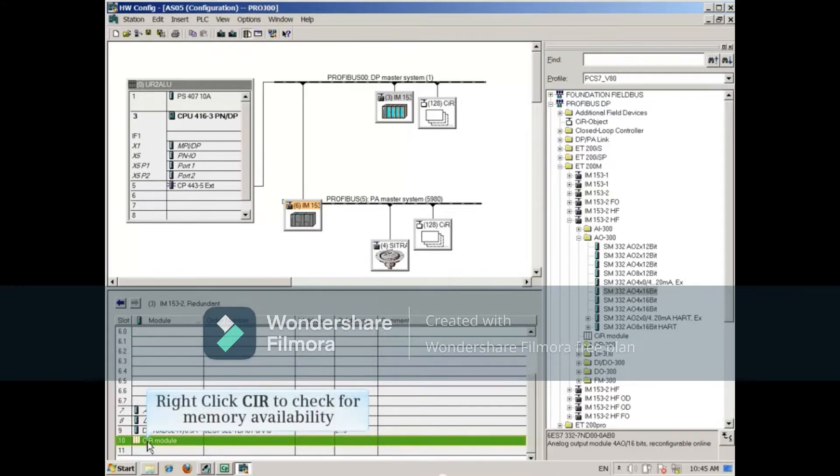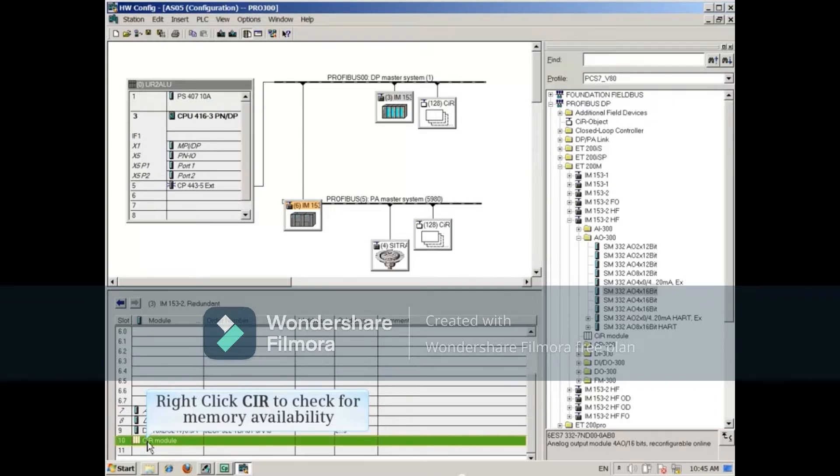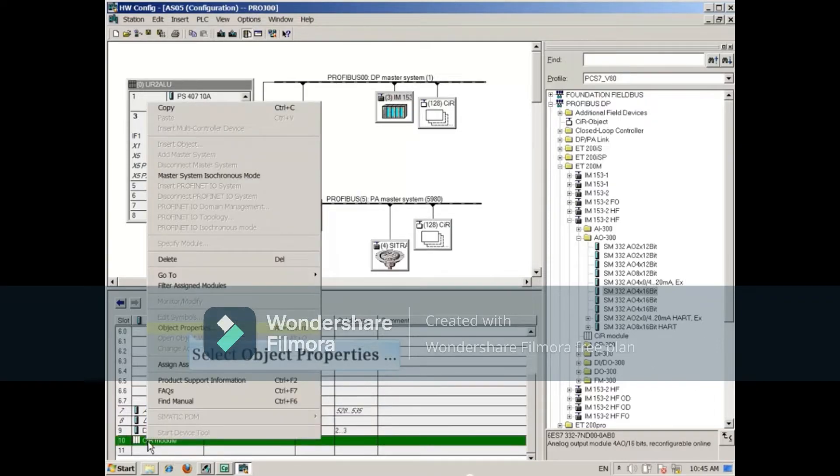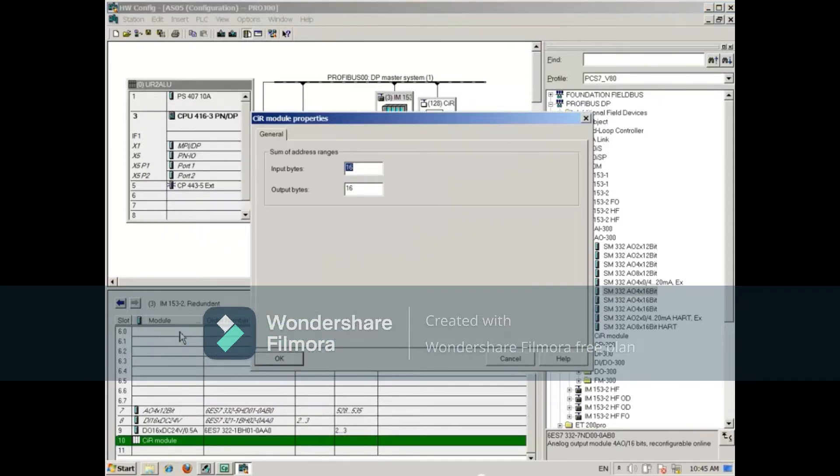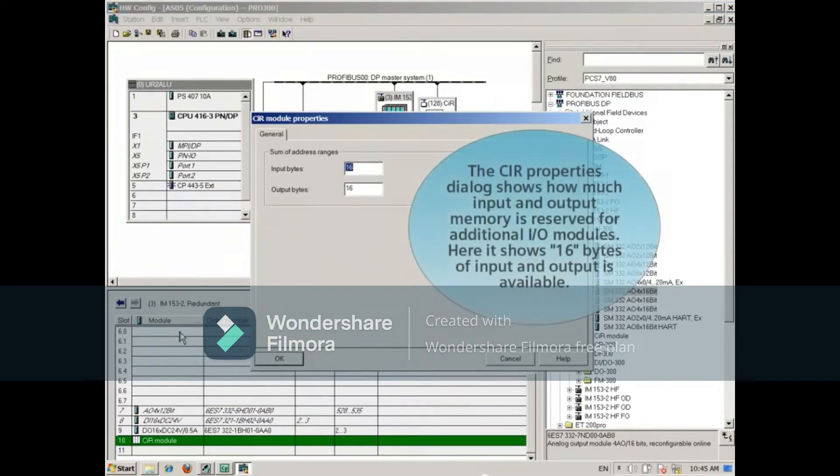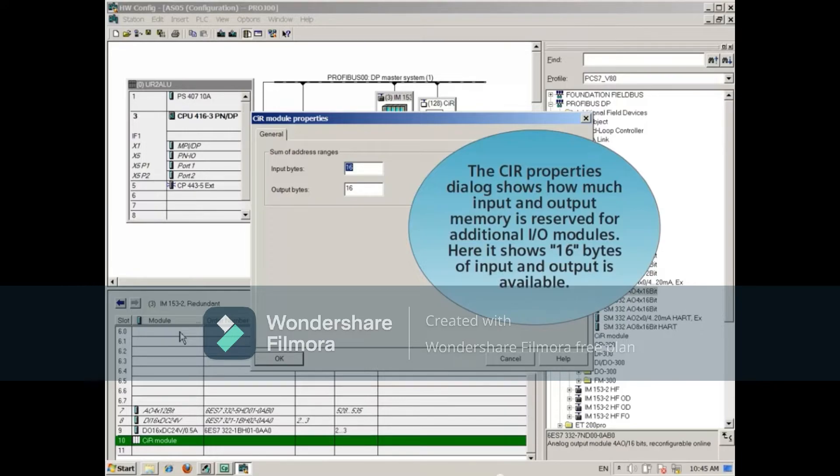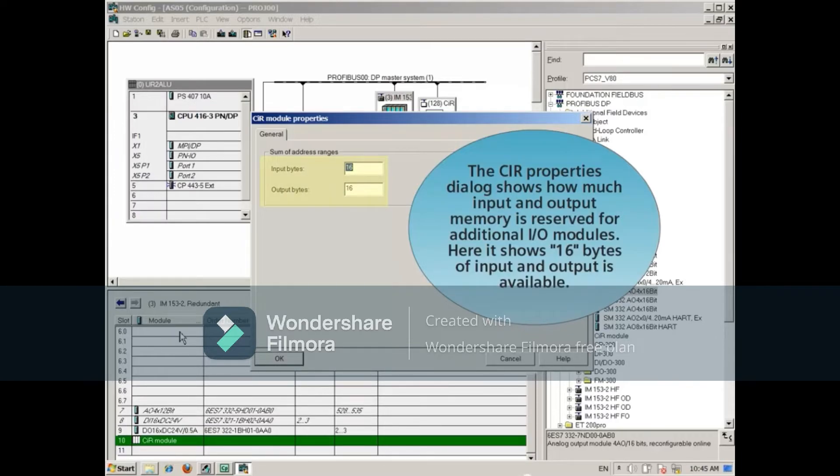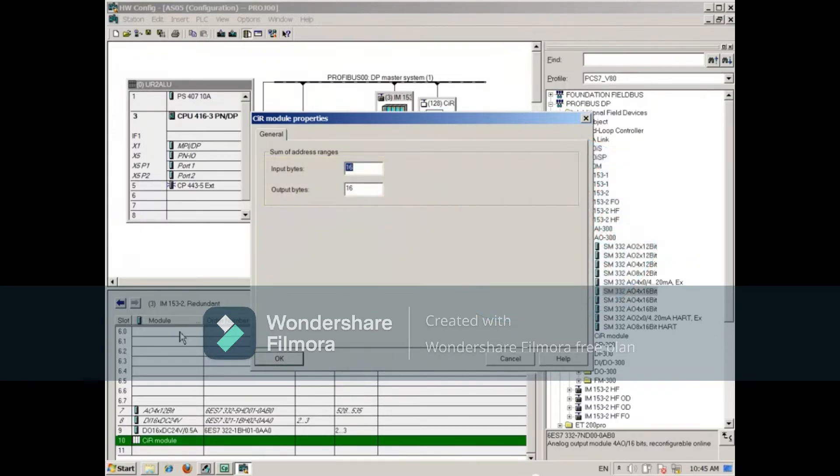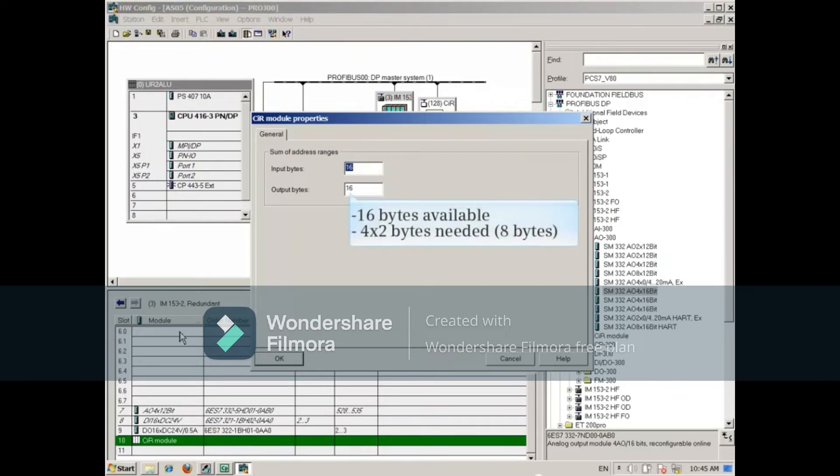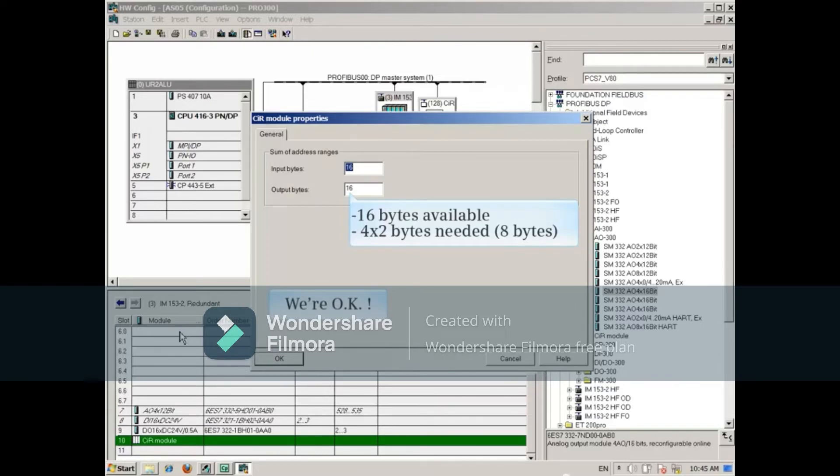To check if it has enough memory to allow the addition of the AO module, right-click it and select Object Properties. The CIR Properties dialog shows how much input and output memory is reserved for additional IO modules. Here it shows 16 bytes of input and output is available. The output module needs 4 times 2 bytes, 16 bits, or 8 bytes total, so we're okay.